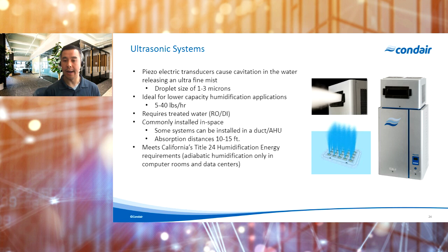Like you see here, some units can be installed inside of a duct or an AHU as well. Now, the thing to keep in mind if you're doing that is, of course, the absorption distances. Because it is a cold mist, we're going to have a plume or visible absorption distance, just like we would with a high pressure atomizing system. With these, we see typical absorption distances in the range of 10 to 15 feet. But again, that really is going to depend on the conditions and where this unit is installed. So of course, warmer, drier conditions where we absorb that water a bit quicker will have much shorter absorption distances.